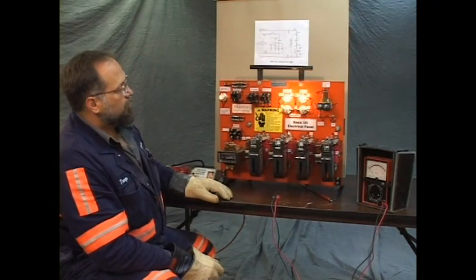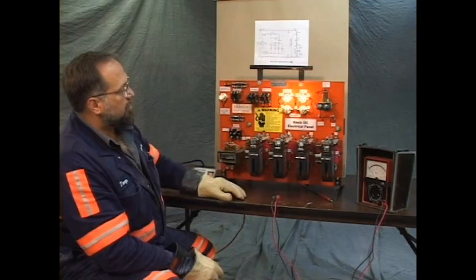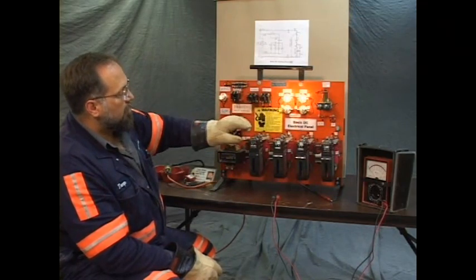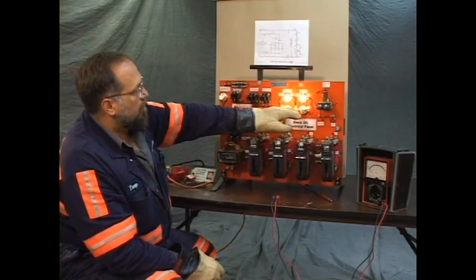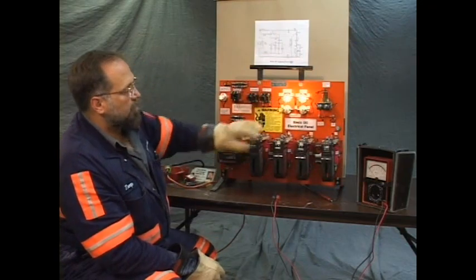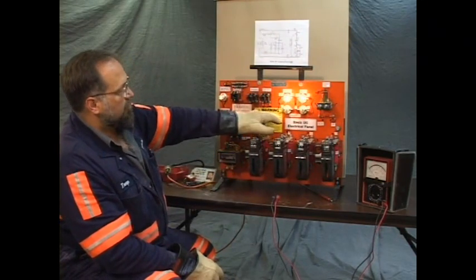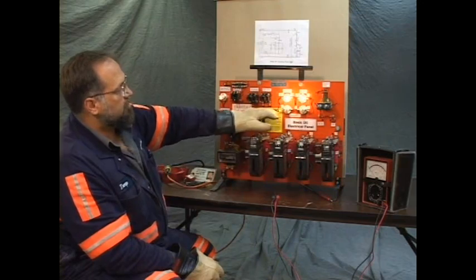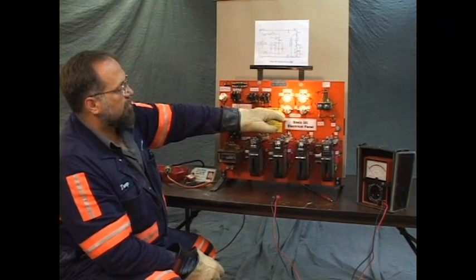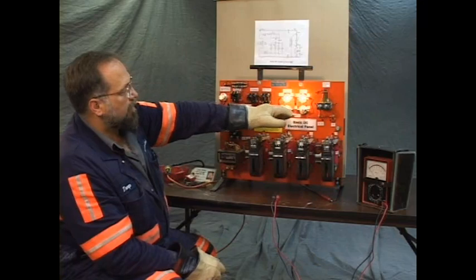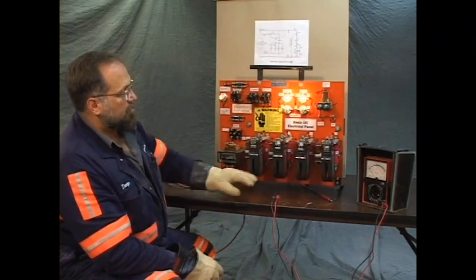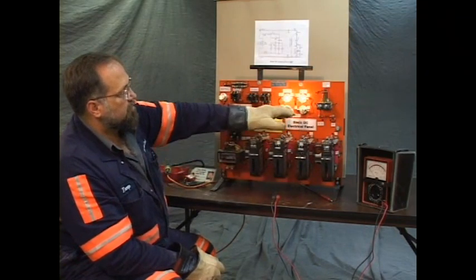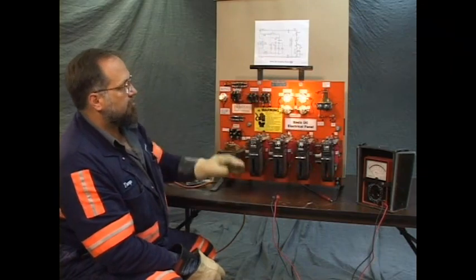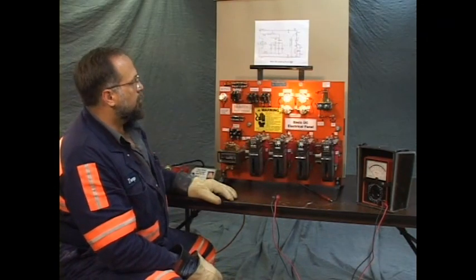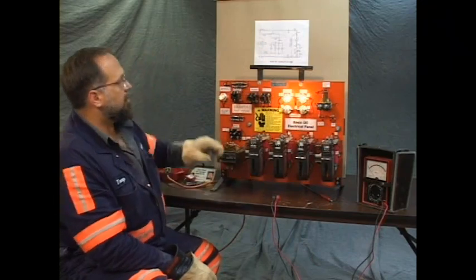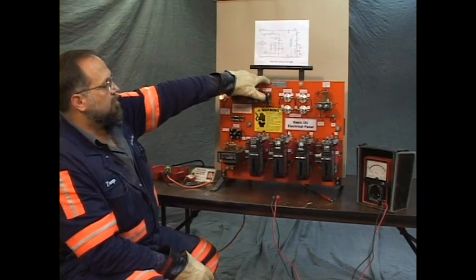The light pattern, normal operation: we'll initially start the panel. All 4 lights come on. These 3, the bottom 2 resistor lights and the armature light, are dim. After the second click, when 1A closes, this starting resistor light goes off. These other 2 get brighter. Third click, when 2A closes, the bottom right light goes off and the armature light is at full brightness, the same as the shunt field. That's normal operation. Watch the lights.